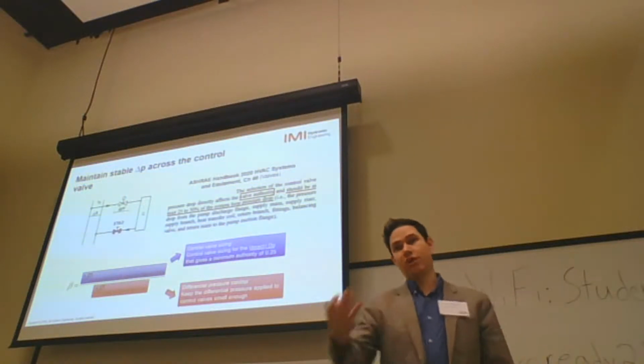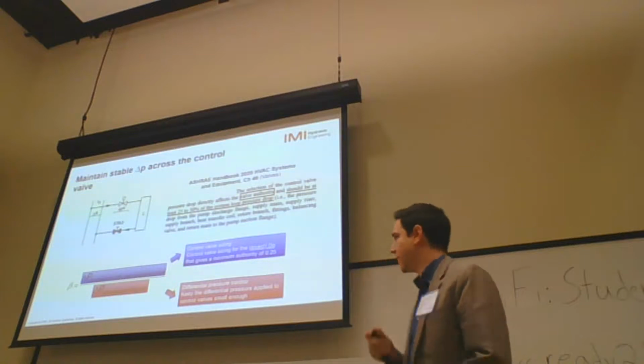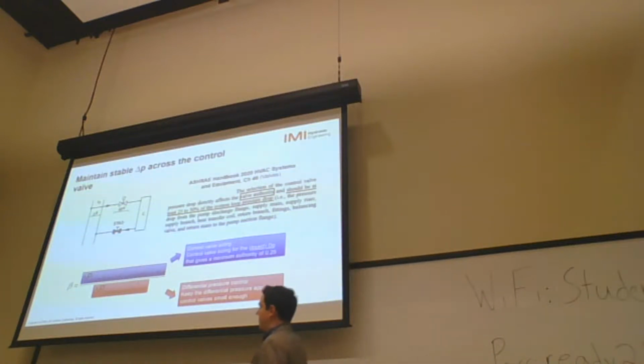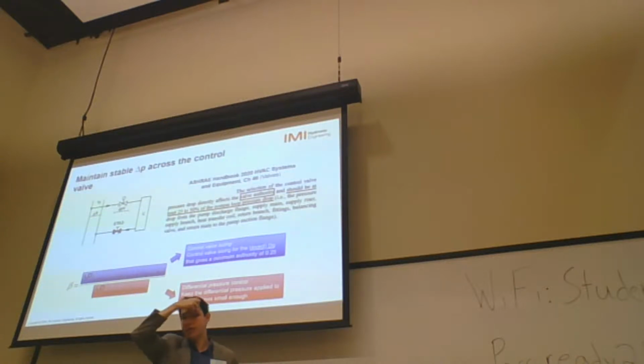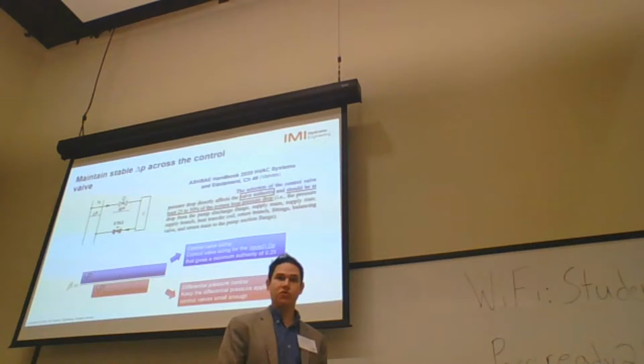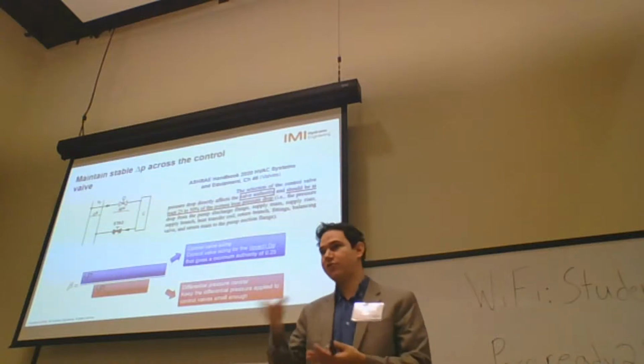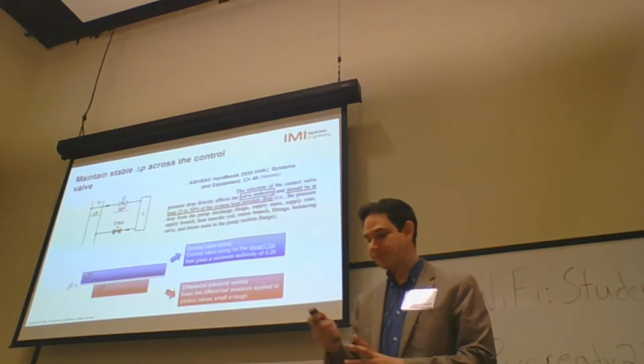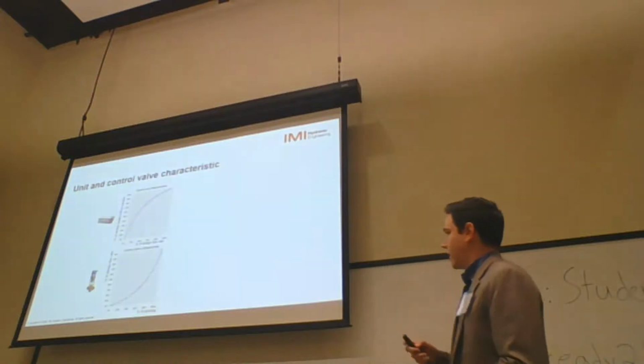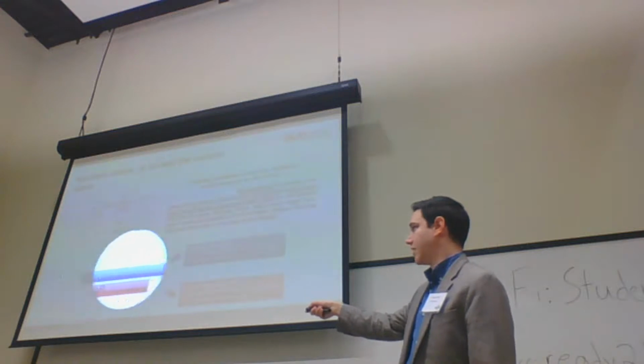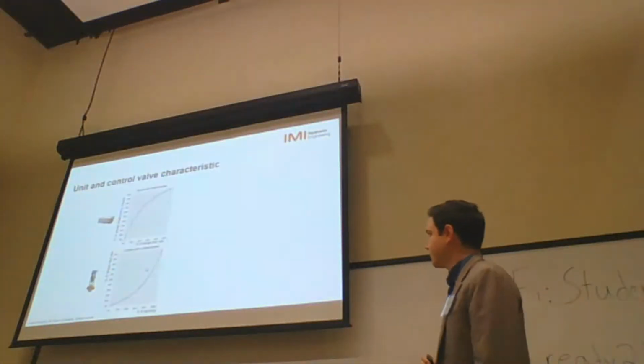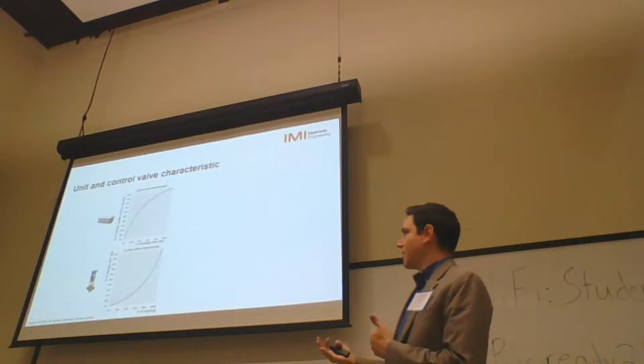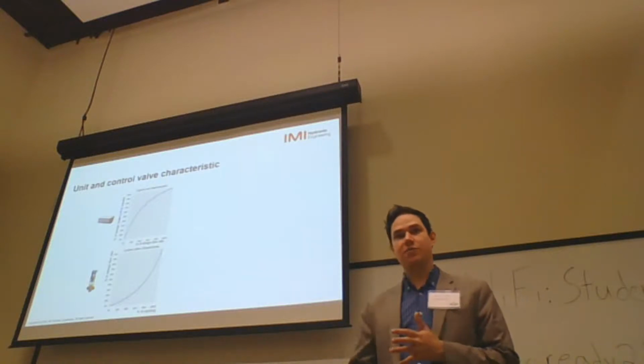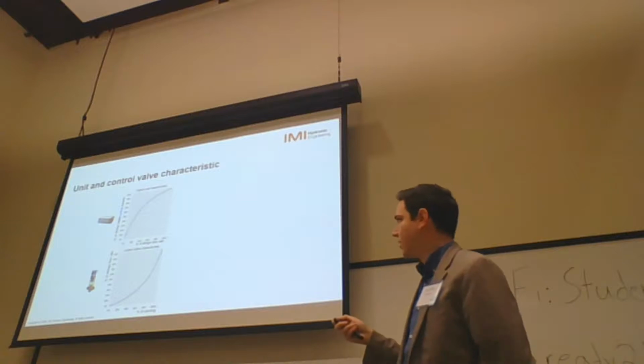On the TAB or commissioning side, what is important is that if I'm able to reduce my pump head, I'm able to reduce the number at the bottom of the equation. So I'm also helping to improve the control valve authority, and the control valve should work better that way. The top part is basically about the selection, so the blue number is the selection of the control valve. Let's understand with a graphical explanation how this works at the job site.